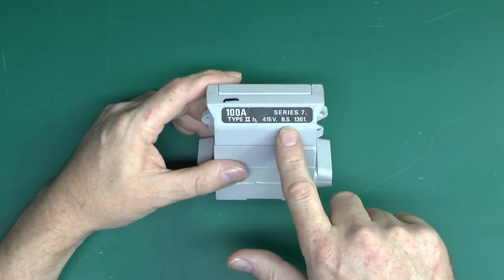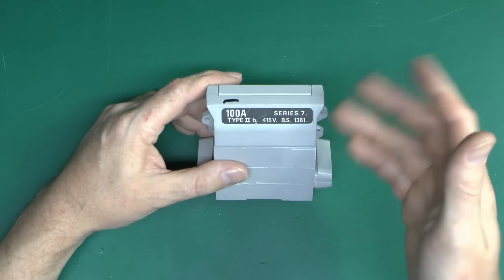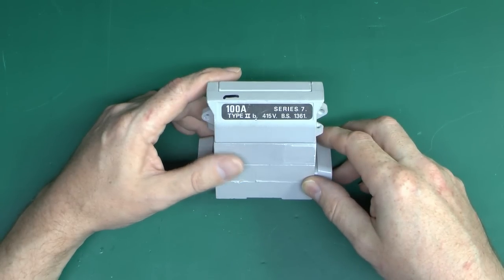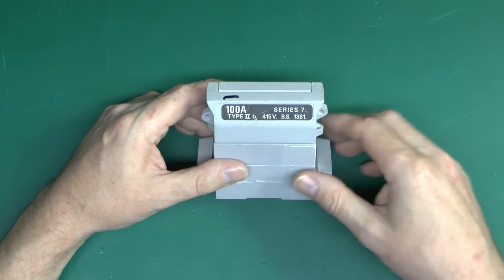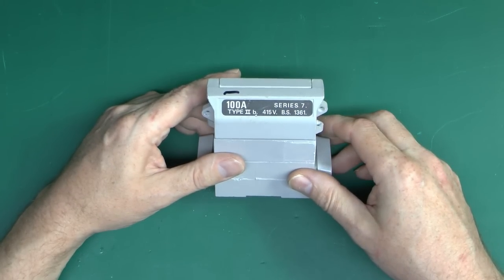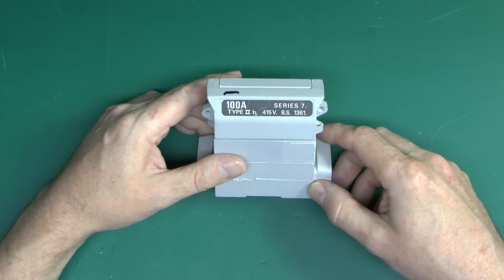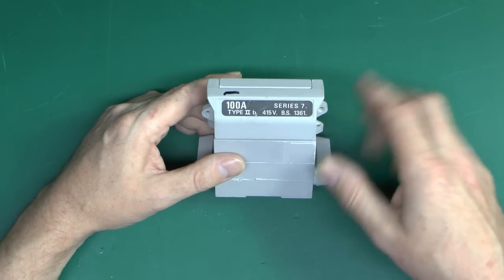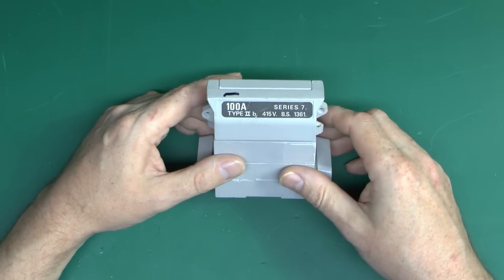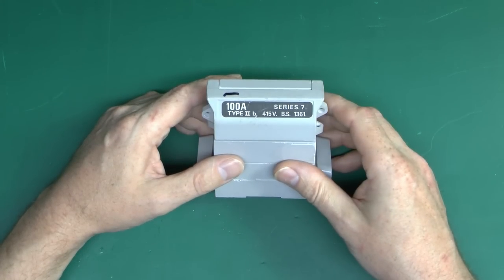This particular one actually has a BS1361 fuse in. That standard is actually now obsolete, it's now BS88 instead, but this being an old one, that was valid at the time. It's also why it says 415 volts rather than the more recent 400. Voltages haven't actually changed, it's just the definitions in various documents that did.